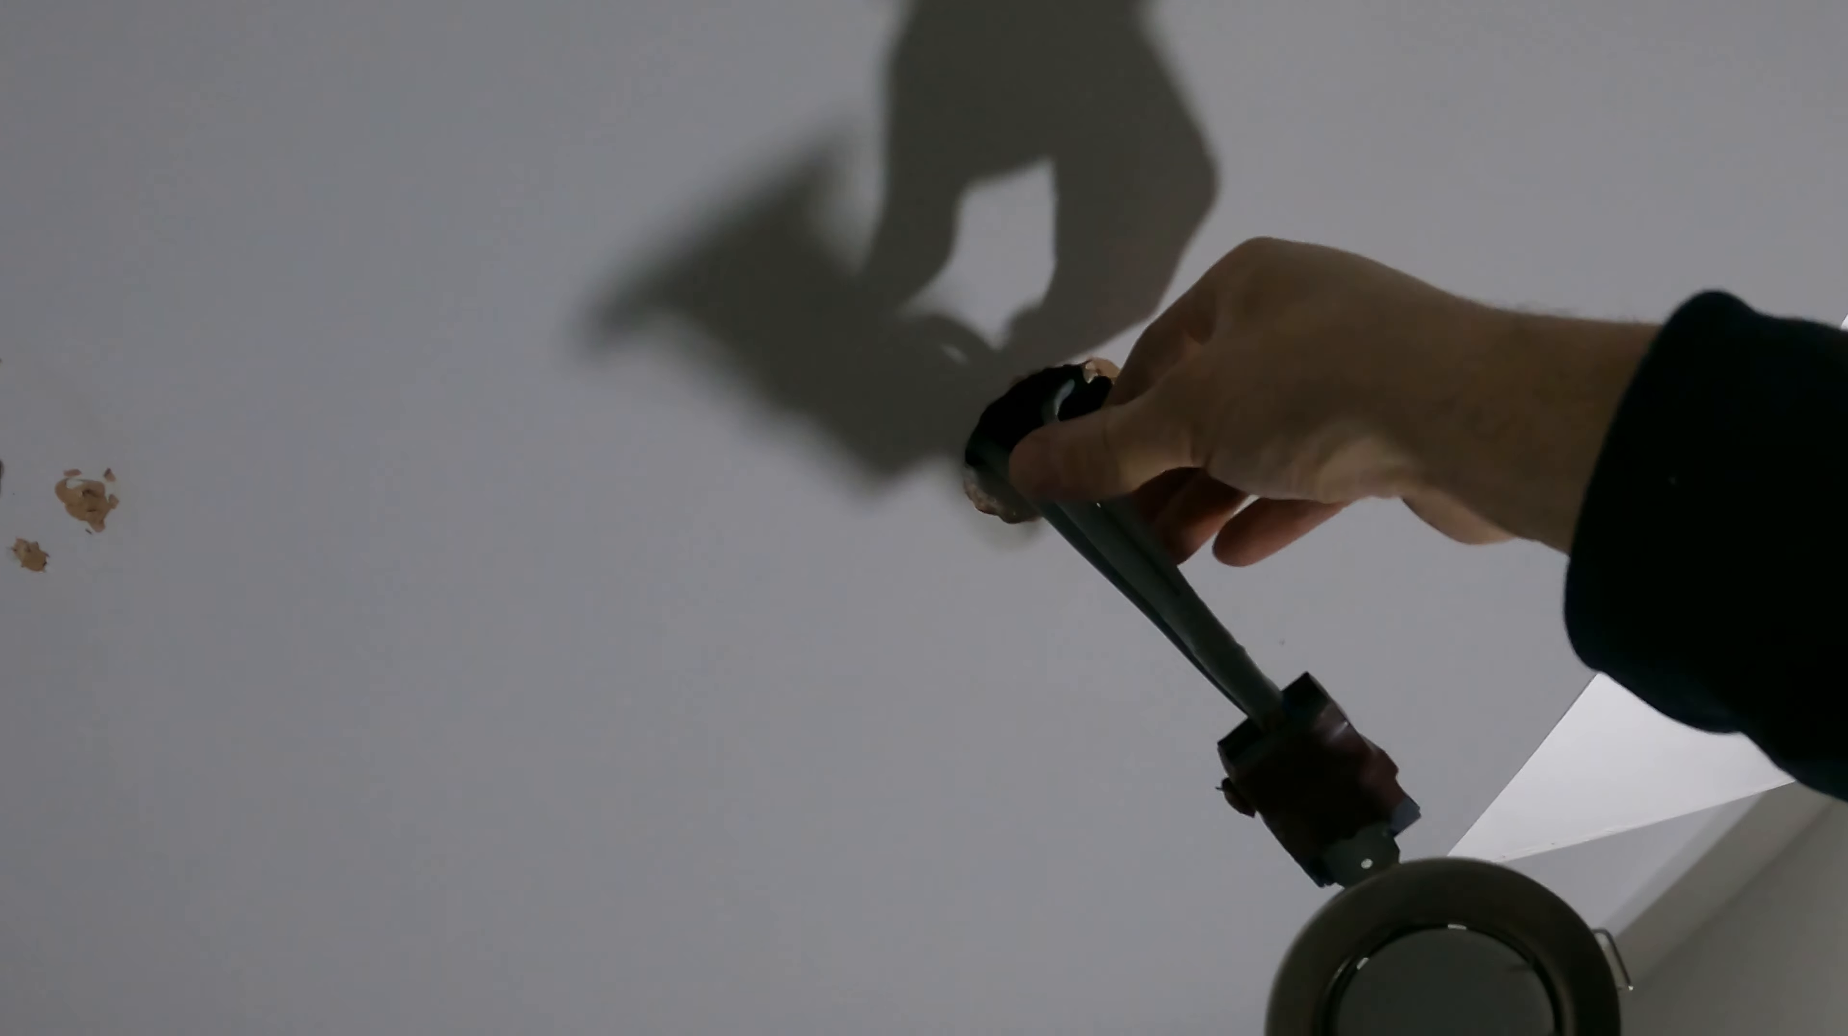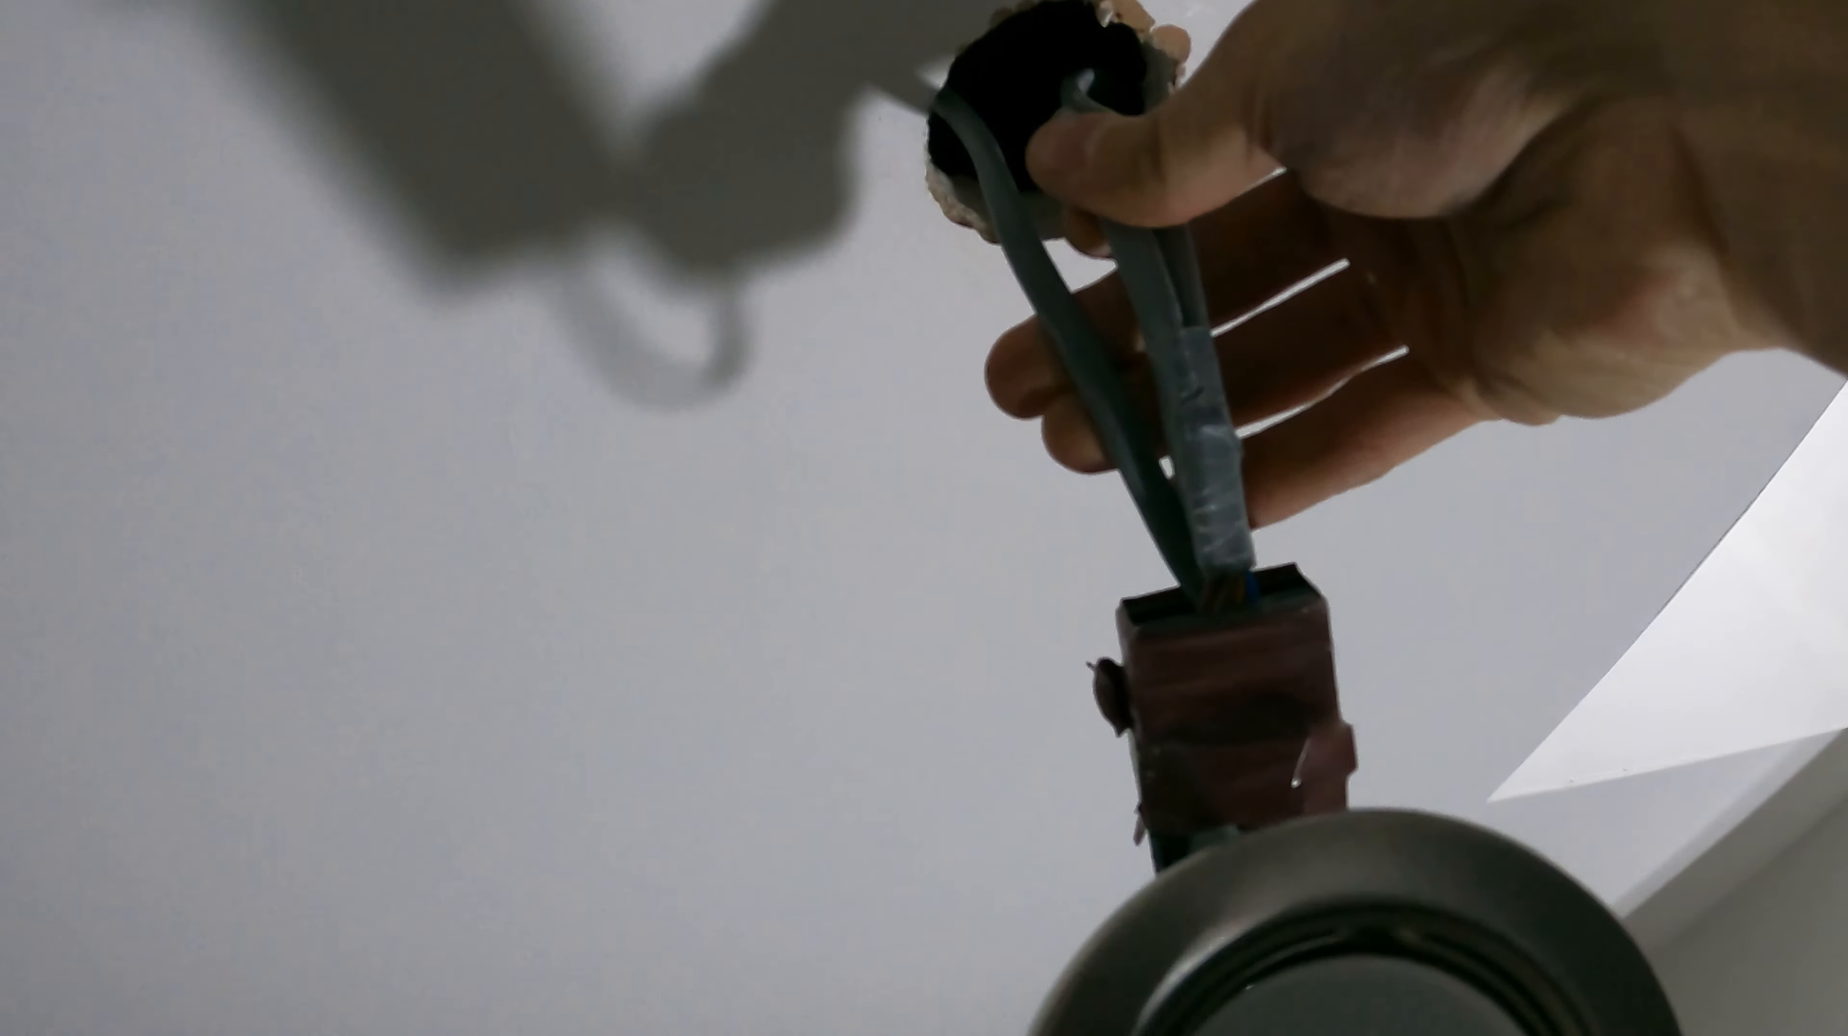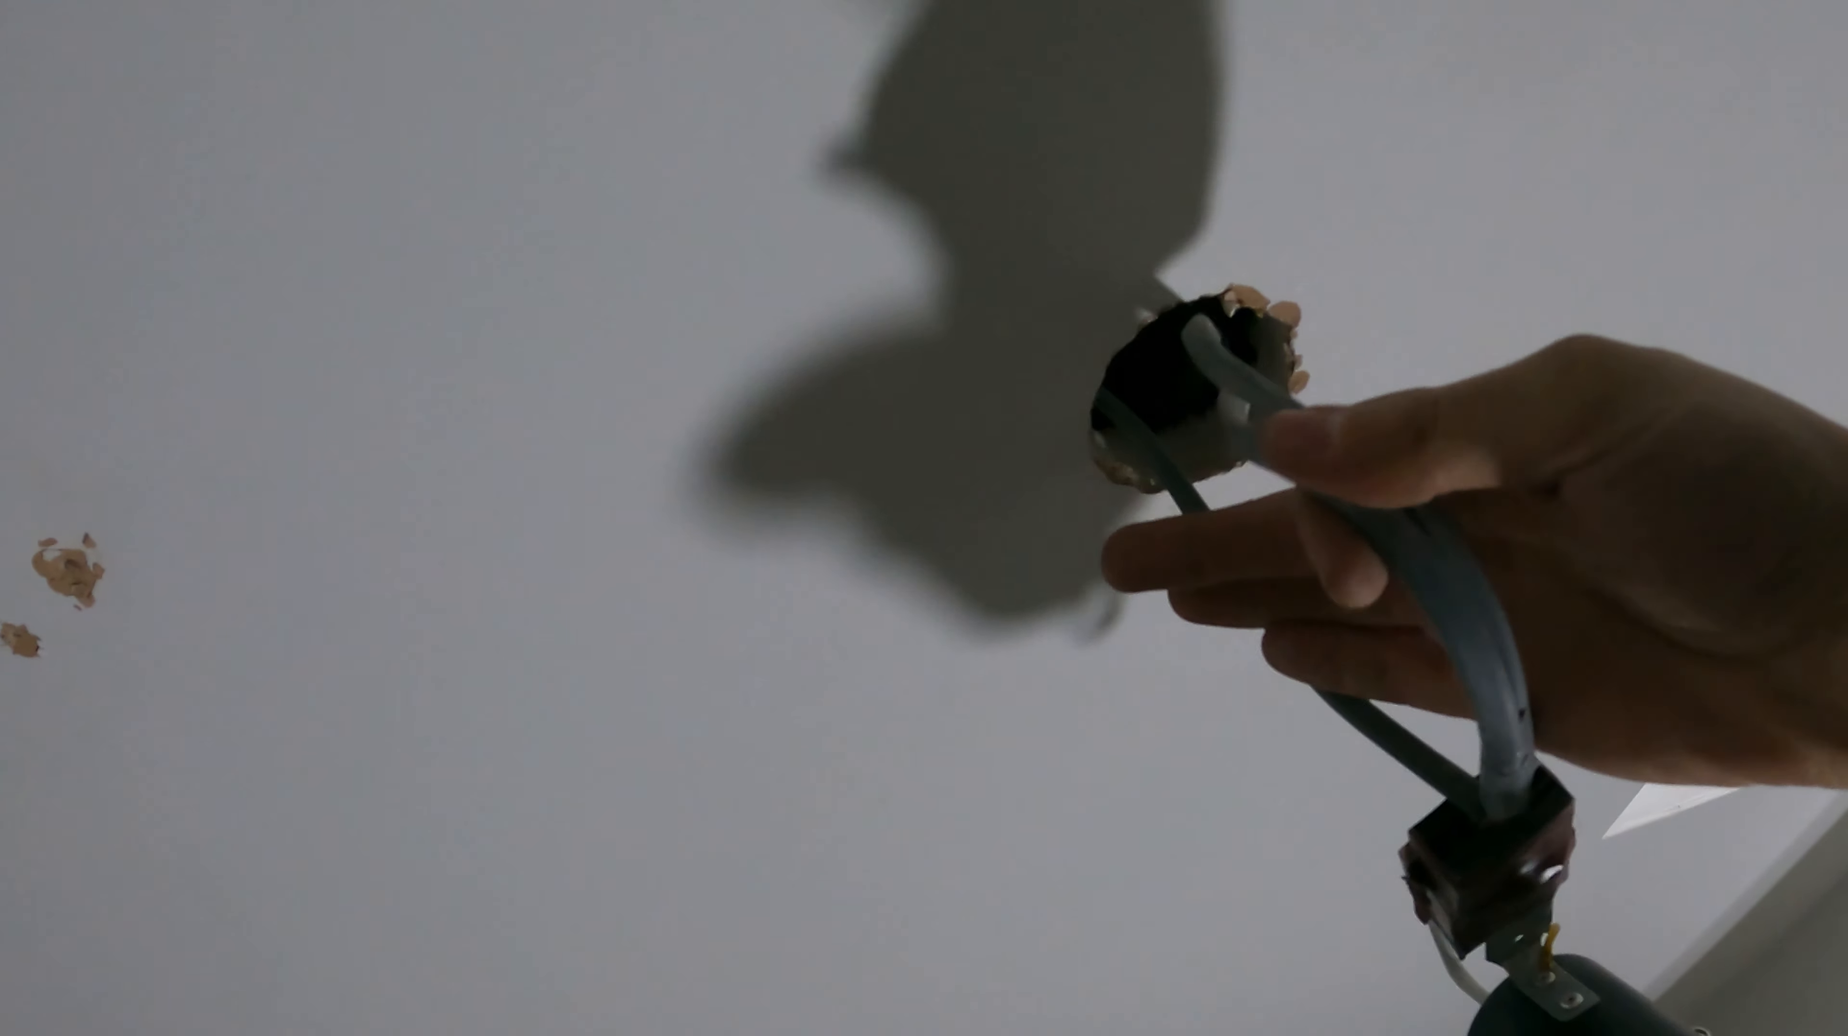And he's not wired this part of the ring, because the light next to it. So he's got his feed in and out, lovely tape job there. At least he's taped it short, I suppose. And that just goes over there, but it's pretty tight, so I can't even just fish that over. So it looks like my plan is not going to happen, really. I'll have to get some rods out and start rodding, see what I can do.